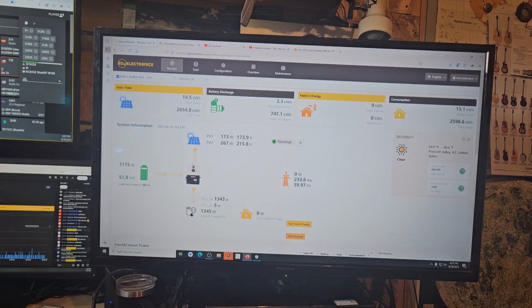We just want to make sure that we get this to where it doesn't trip the BMS. I just need to get it to where there's a safe cushion. Because once the BMS trips, then we get all these other problems, and then you got to either wait for the battery to rejuvenate, or go in there and jump it. Last time I did that, it took a chunk out of the terminal, so I don't want to do that again.